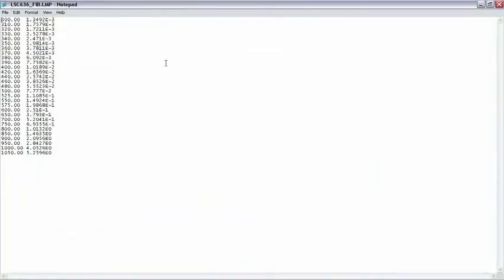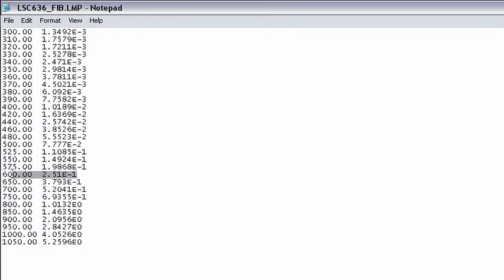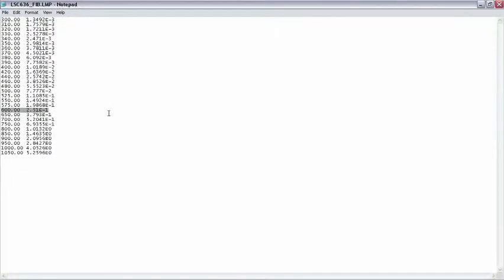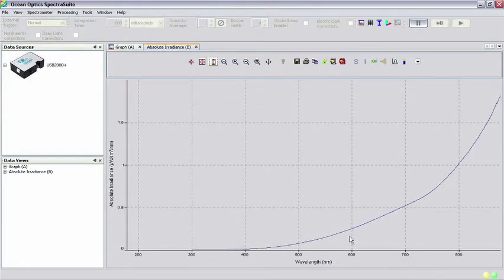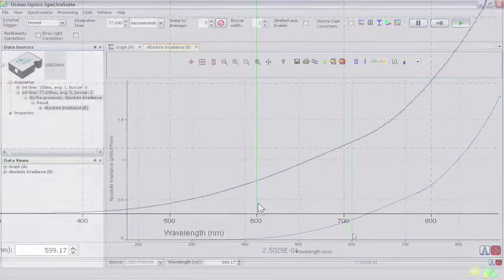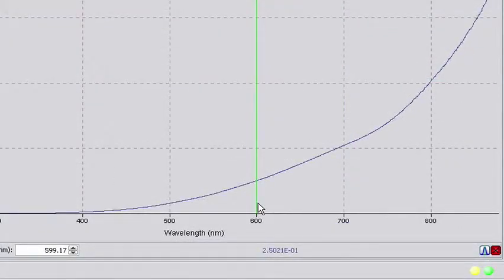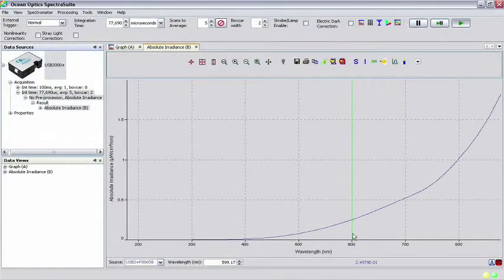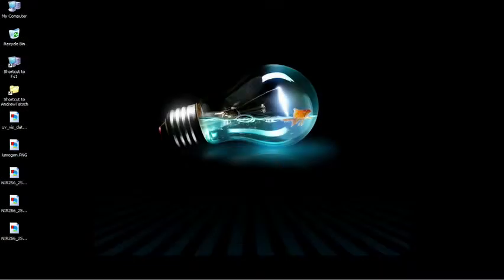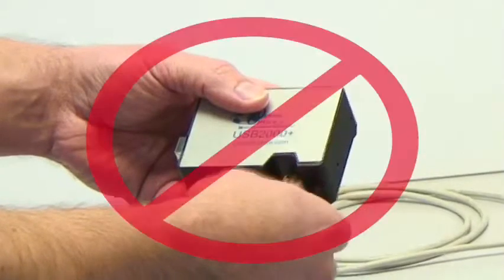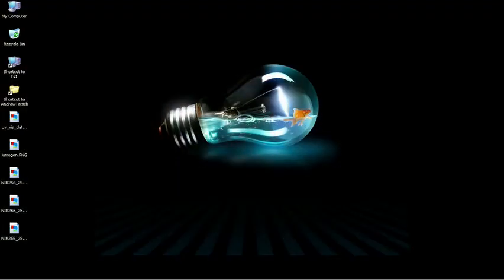For instance, our lamp file shows a value of 0.251 microwatt per nanometer at 600 nanometer. Clicking on the spectrum graph at 600 nanometer to activate the cursor, we see that the value at 600 nanometer is approximately 0.25 microwatt per nanometer. Therefore, it appears we have done the calibration correctly. Once your system has been calibrated, you do not need to recalibrate the system each time you wish to take a measurement, provided you have not removed the fiber from the spectrometer. You have calibrated the fiber and spectrometer as a system, so any alterations to that system will mandate a recalibration.